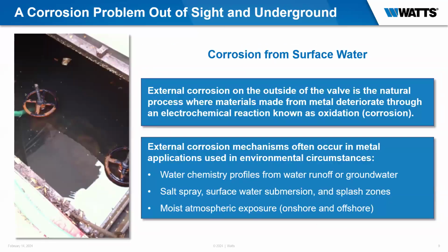Something you don't see in buildings much, but outside, in the yards of industrial parks or commercial buildings, you have vaults, and those vaults do get flooded. That's a lot from water chemistry: runoff of groundwater, salt sprays, surface water submersion, splash zones, depending where you live. Everybody sees that salt going down on the ground for ice, and then where's that all getting washed to? Sewers, driveways, everywhere. Everybody uses salt, and that's highly corrosive, and it gets washed somewhere.